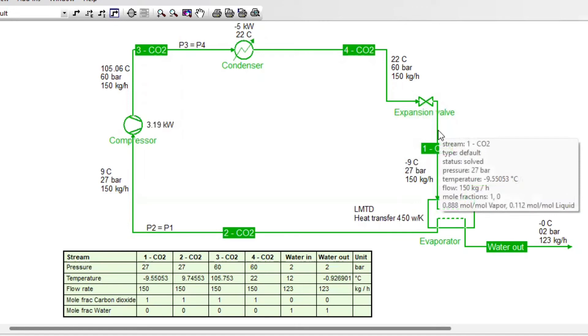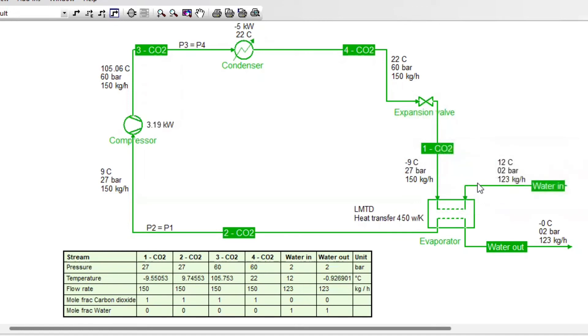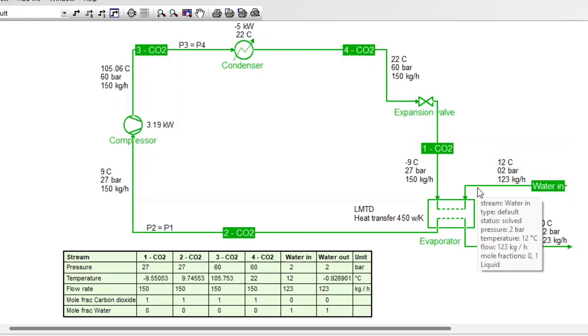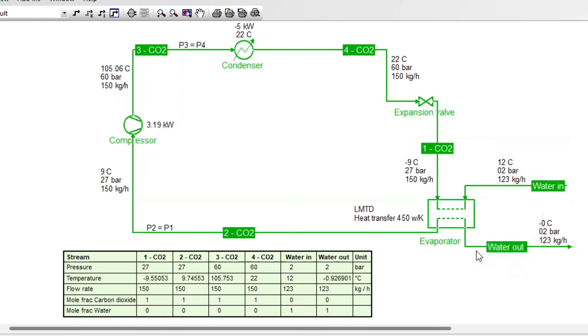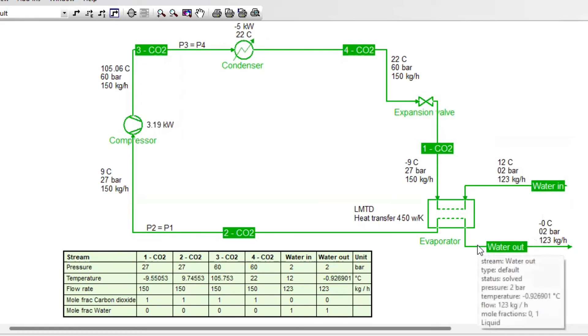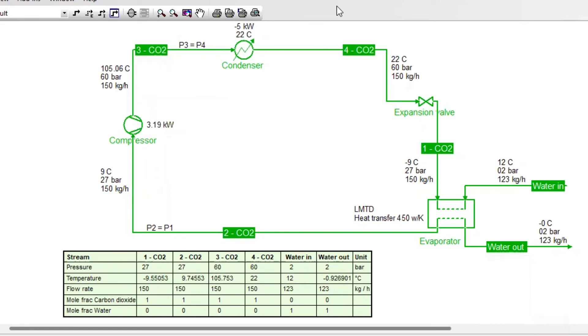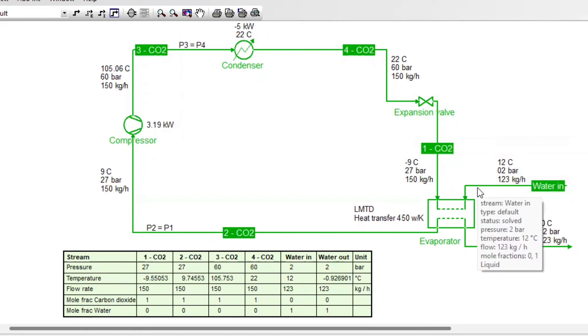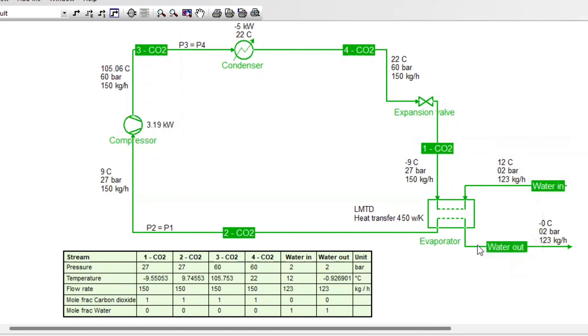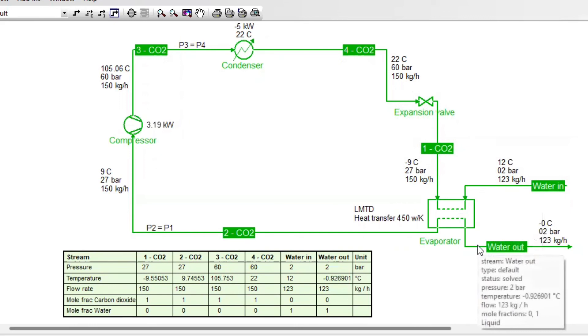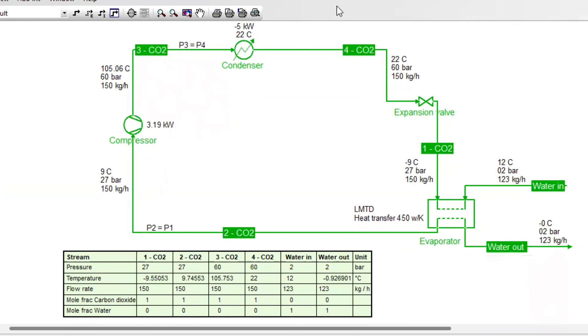Step three is the throttling step — the expansion valve. Pressure-wise, carbon dioxide moves through the expansion valve, which is the gateway into the area of low pressure. Step four is the evaporator — in this case we use the heat exchanger. Here, carbon dioxide is at low pressure and low temperature. During this stage, heat is transferred and water is cooled from 12 degrees to minus zero degrees, which is our desired aim. We used carbon dioxide as the refrigerant. I really hope this was fun and you enjoyed solving it with me. Feel free to comment or send me an email — thank you so much for watching, till next time!